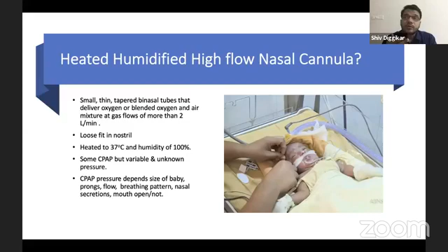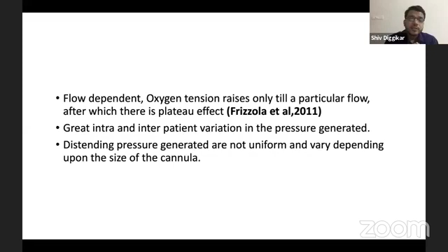CPAP depends on various factors. First is the size of the baby, the prongs, breathing pattern, nasal secretions, and whether the mouth is open or closed. If the mouth is closed, the CPAP pressure goes very high. Again, it's flow dependent. The oxygen tension rises until a particular flow, after which there is a plateau effect, and after this you cannot increase the oxygenation. There is great intra and inter-patient variation in the pressures generated, and you can't measure it. Distending pressures are not uniform and vary depending upon the size of the cannula.